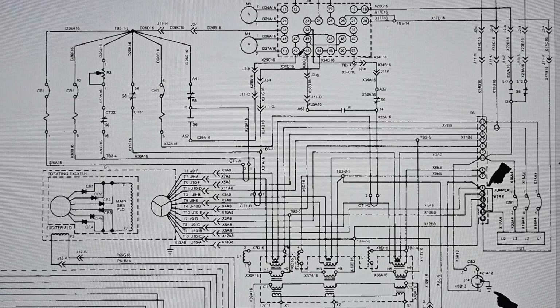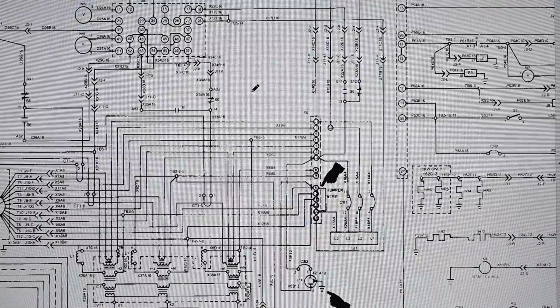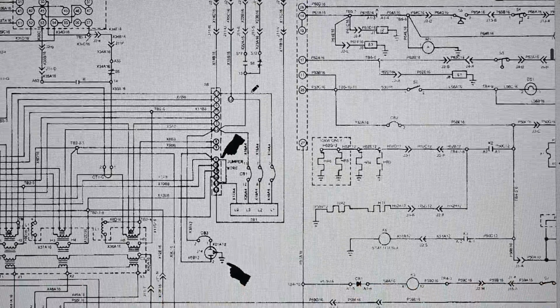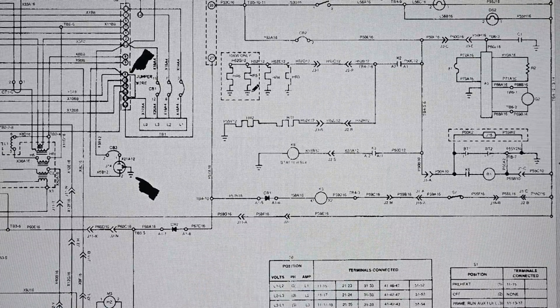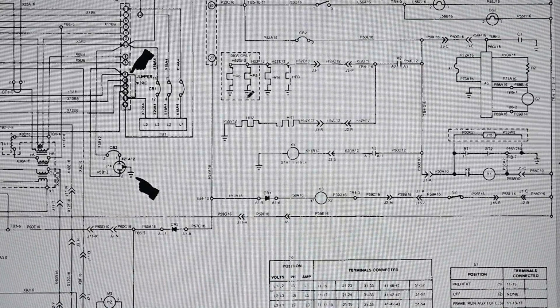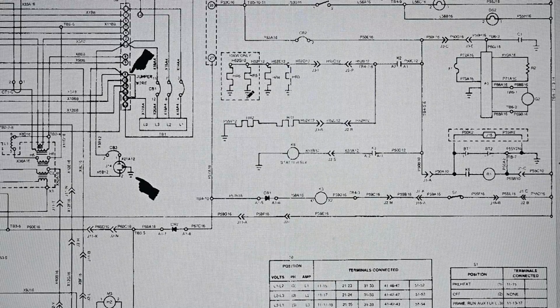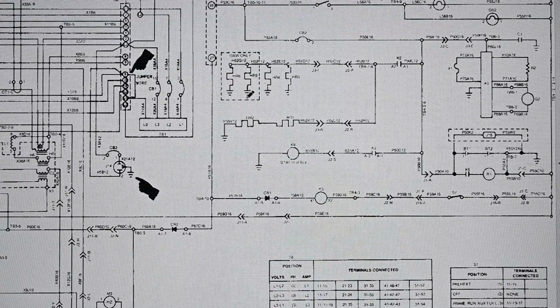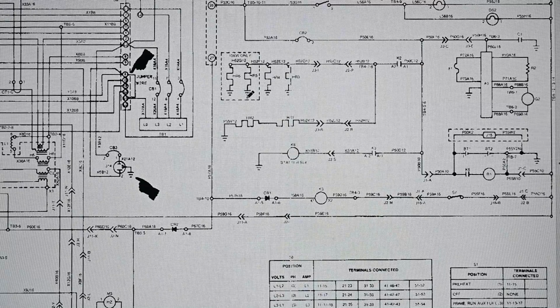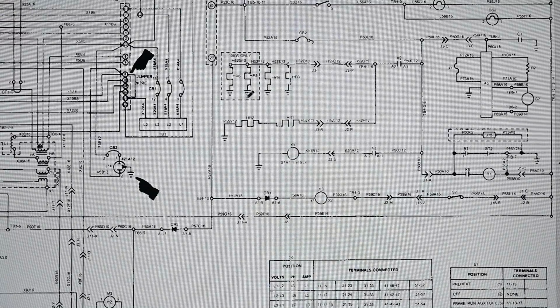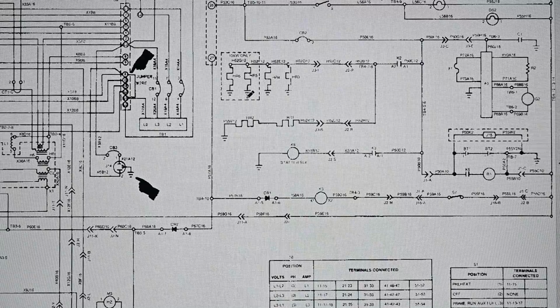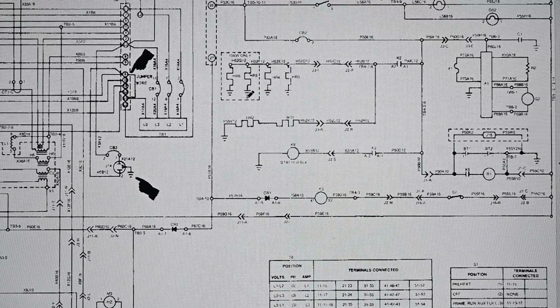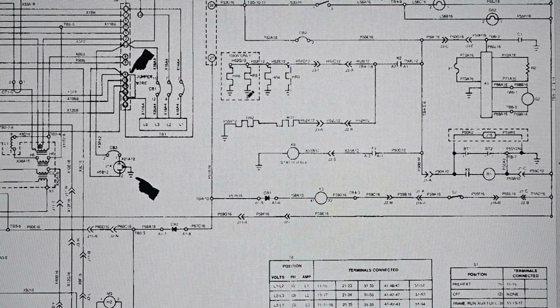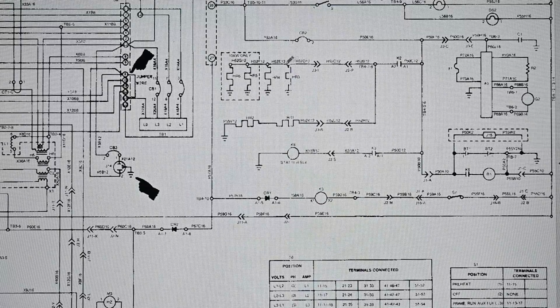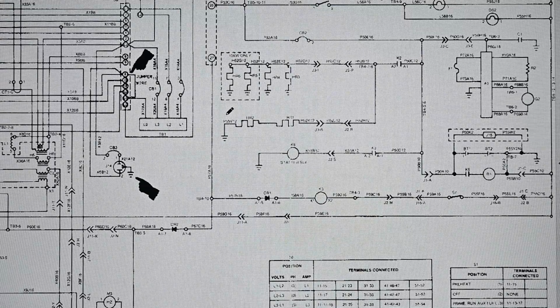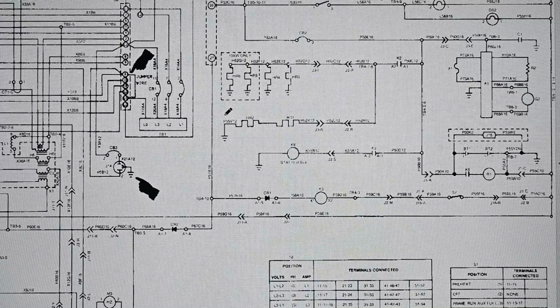And the first thing that actually happens is when the engine is started, the alternator's field is flashed. And what does that mean? Well, you have to apply a DC voltage to the alternator's field to create the initial voltage, because if you just have the alternator spinning but do nothing else, there's not enough residual magnetism to create a voltage and to build things up and have the regulator take over. So to get that initial voltage, the term is to field flash, and that's done automatically when the engine is started, and as the engine is coming up to speed, the voltage is applied to the field.